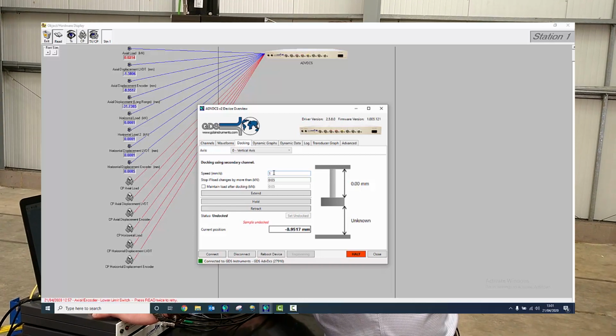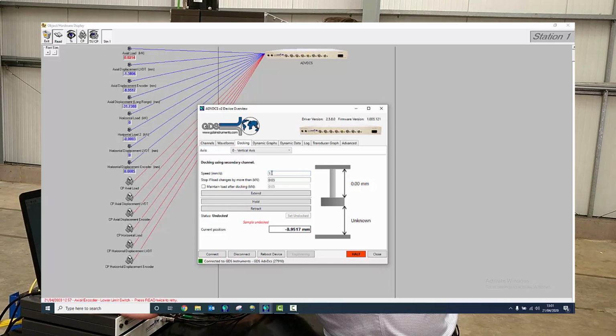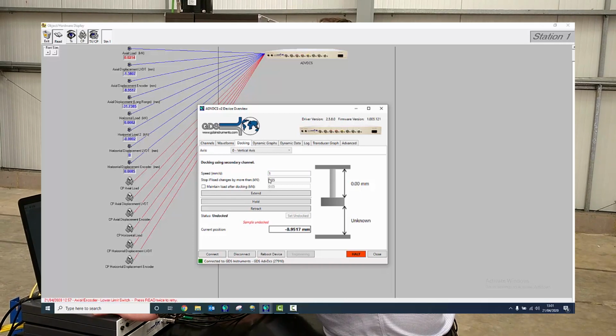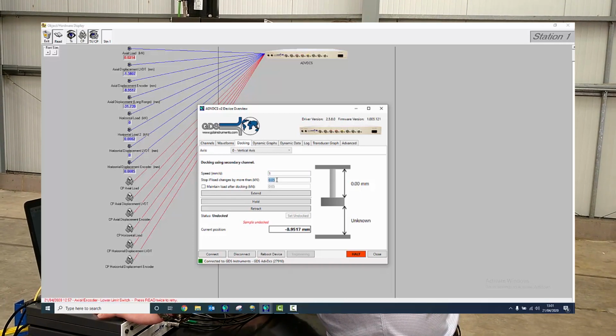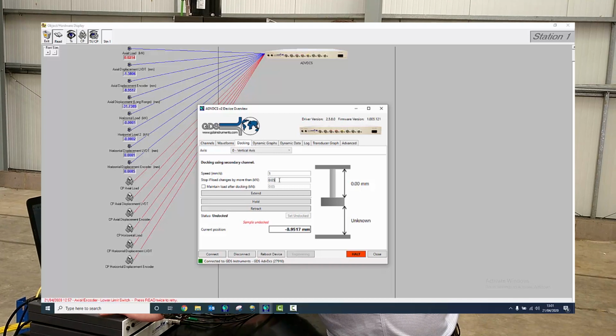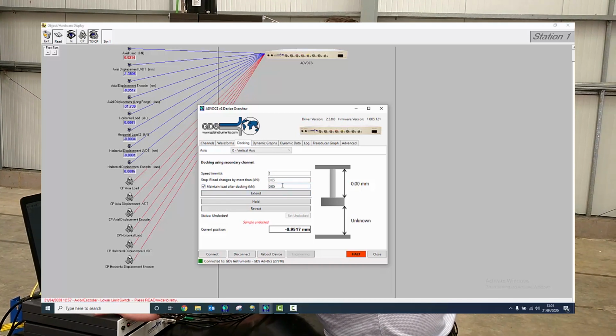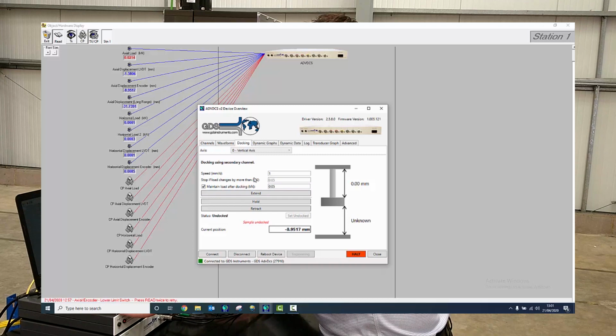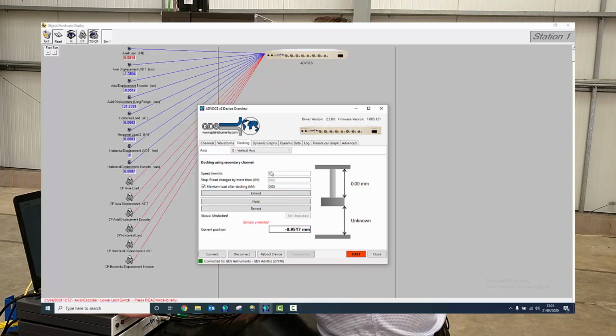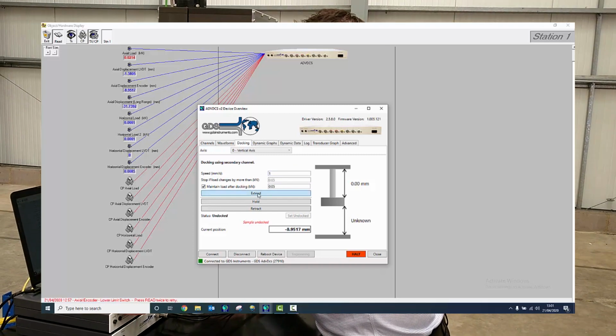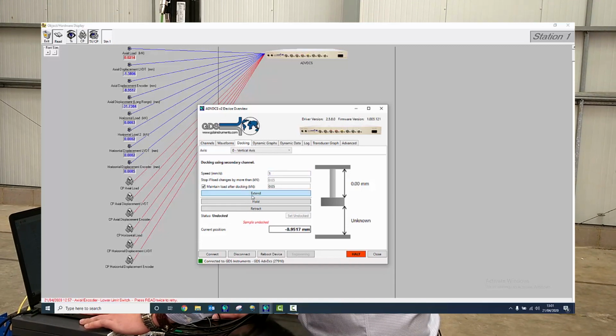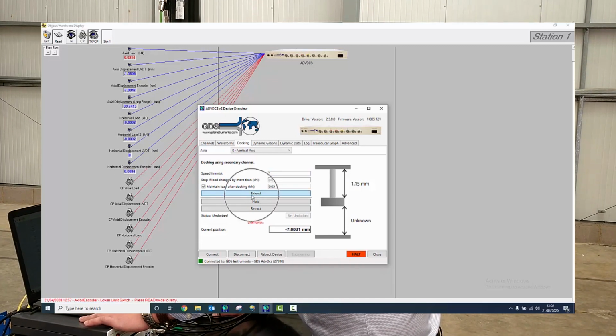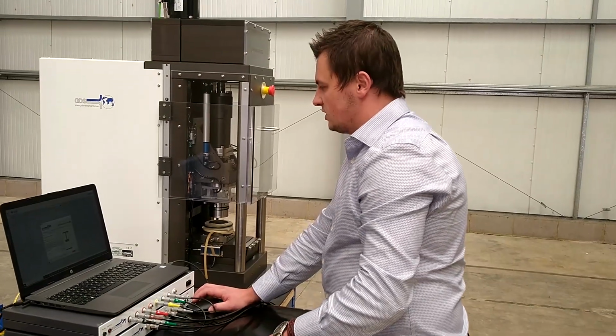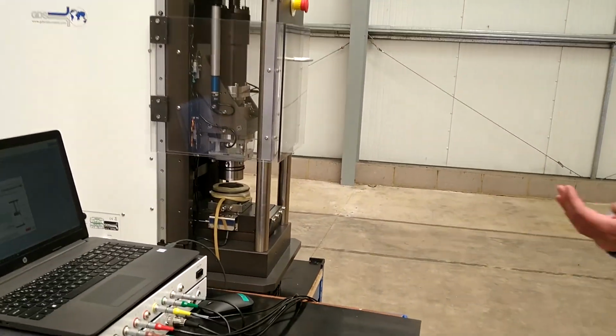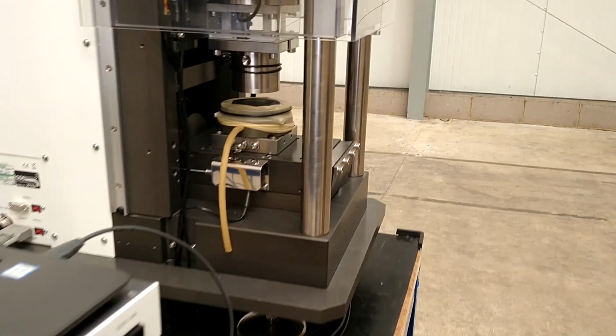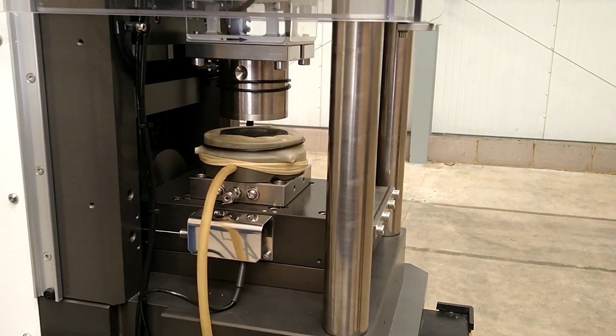We'll move down at the speed of 1 millimeter per second, and then we'll consider 0.05 kilonewtons as the docking load, and we want to maintain that force after the sample is docked. All of those parameters can be changed to suit the needs of the testing and the sample. And now I can just click extend. And as you can see, the machine will start moving down until it touches the sample.